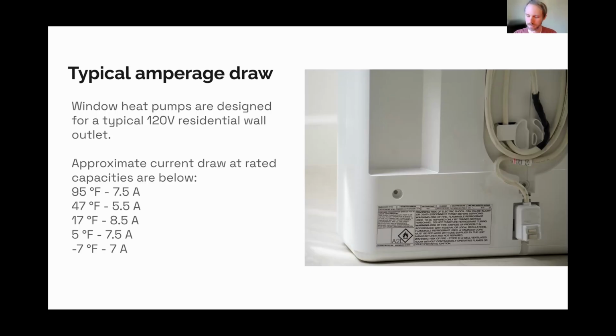So really, the driver for Clean Heat for All asking for no backup heat — which has pushed a lot of products in this category to drop it — is that if you add backup heat, you probably need an electrician and you're way increasing the cost. It's actually not the cost of energy, it's the cost of the electrician that makes backup heat prohibitive. For what it's worth, I've run a cold weather heat pump with no backup for 4 years now, no problem — just wanted to share that.